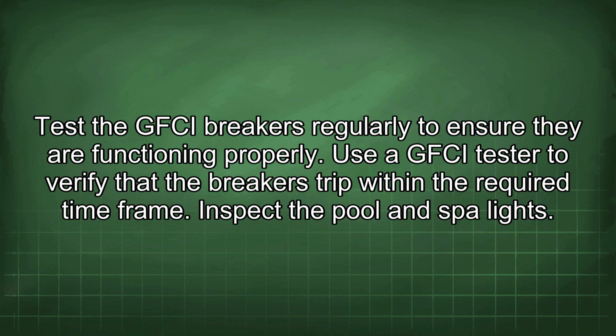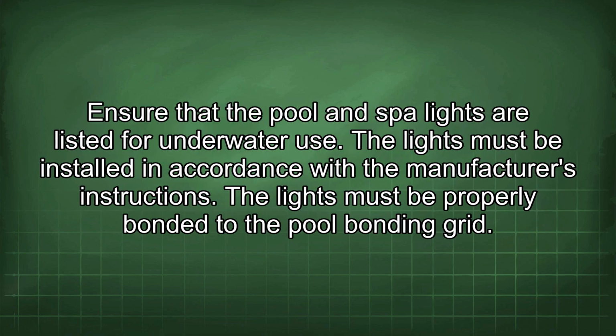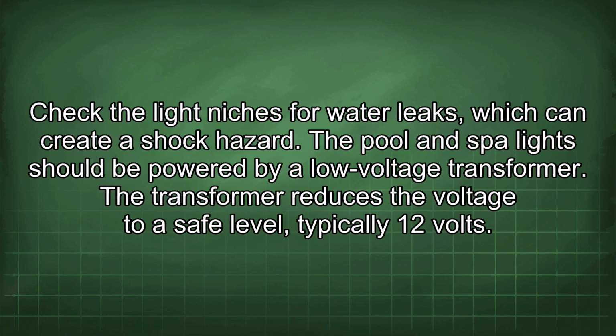Inspect the pool and spa lights. Ensure that the pool and spa lights are listed for underwater use. The lights must be installed in accordance with the manufacturer's instructions. The lights must be properly bonded to the pool bonding grid. Check the light niches for water leaks, which can create a shock hazard. The pool and spa light should be powered by a low voltage transformer. The transformer reduces the voltage to a safe level, typically 12 volts.